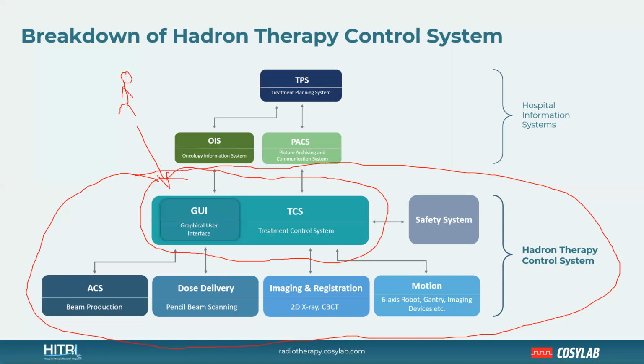So then we have the accelerator, the beamline, and a dose delivery system, which is typically a pencil beam scanning system. Then you might have either a 2D X-ray system or a CBCT imaging system in the room. You also have to be able to control it and communicate with it. And there are typically numerous devices that also move inside the room: a robotic couch, the gantry rotating around the patient, and imaging devices that might retract and move around. So all of this has to be under control.